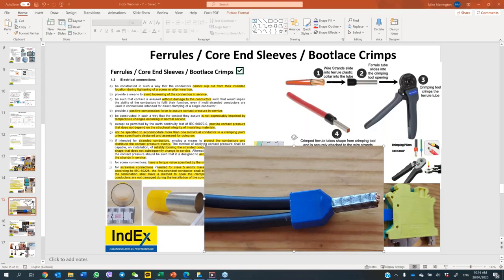Somebody mentioned heat tracing. It's a contentious issue. Yes, twisting the wire in a ferrule is not allowed. You pre-twist the wires. Some manufacturers call for it, some do not. When you pre-twist the wire, it ensures that none of it goes off and frays. But once again, always read the certificate, the IOMs, and the standard. Problem is not all of you have the standard, or the IOMs, or any of these things.